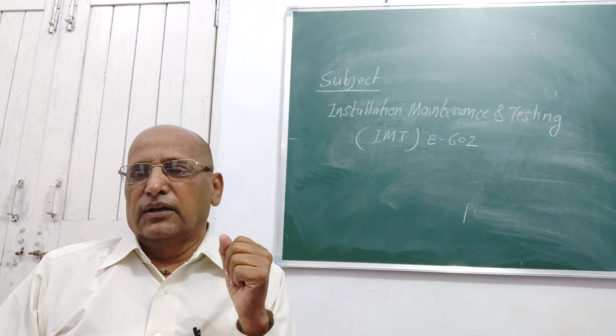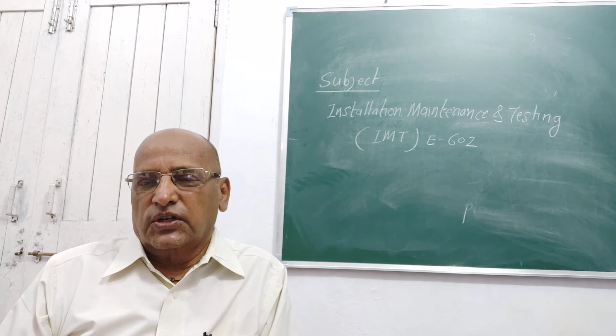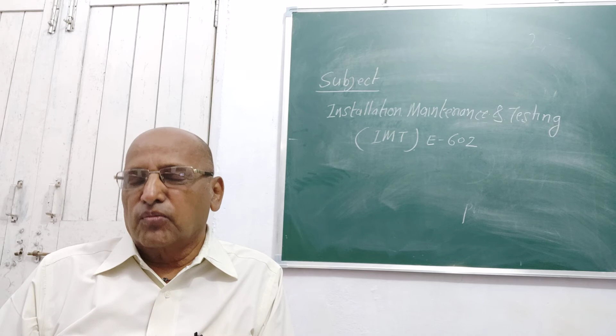So they are supposed to be heavy equipment. Lifting of these is done with a chain pulley block or with the help of pulley and ropes. These are used for lifting the AB switch, lightning arrestor and DO fuse to install at a particular height as per the specification given on the drawing. They are tightened properly with the rope and pulley, then lifted or pushed up with the help of persons, and when fitted on the proper space, they are fixed with nut bolts and clamps in the proper position. So this is the installation of a pole mounted substation.